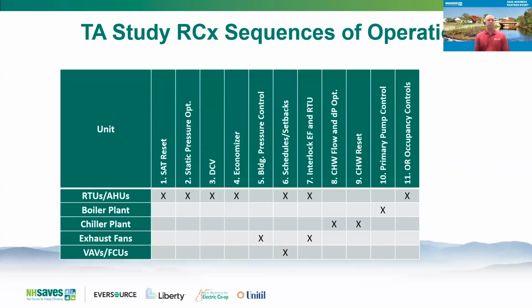So again, the sequences in this project included 11 across not only rooftops and air handlers, but also the boiler plant, the chiller plant, exhaust fans, as well as terminal units. So it included supply air temperature reset, static pressure optimization. This one included demand control because in a hospital facility, so long as it's an appropriate space, demand control can be a very good opportunity because there's a lot of varying occupancy in a hospital. Again, the economizer sequence we just pointed out. This building had exhaust fans that were just running constant. So we put in a pressure control sequence to basically run those fans to maintain a pressure, so they're not just running all the time.